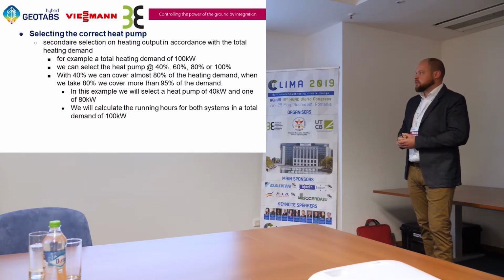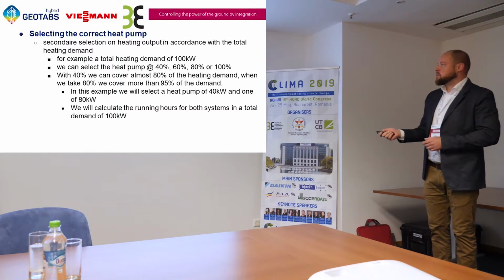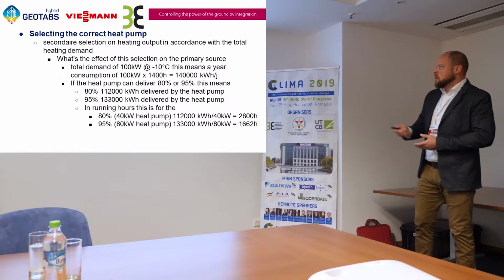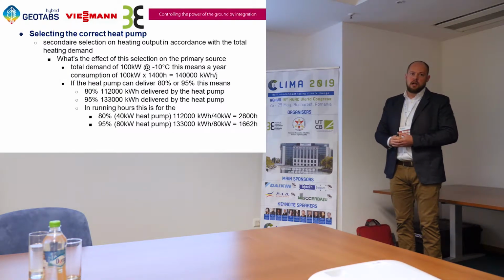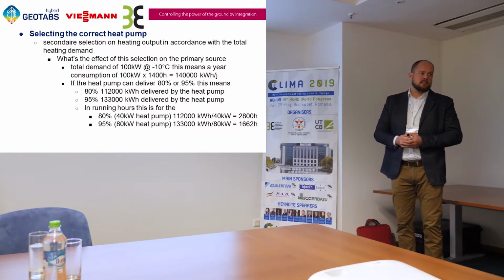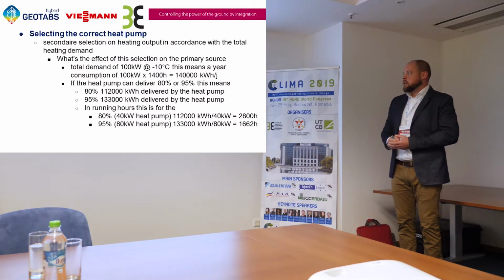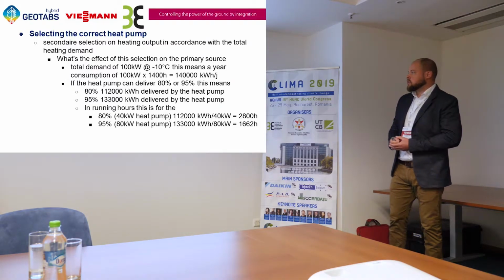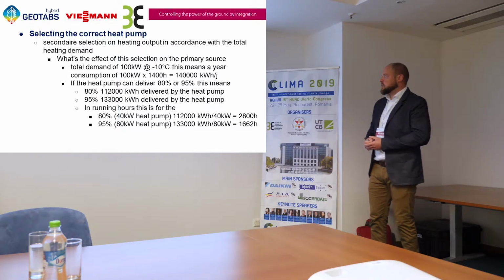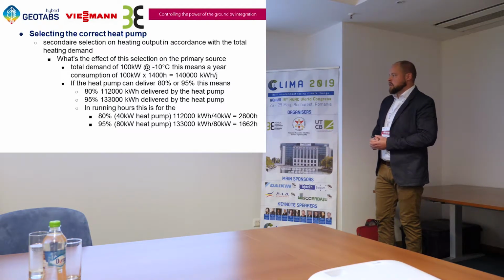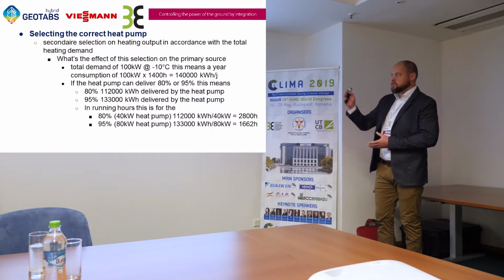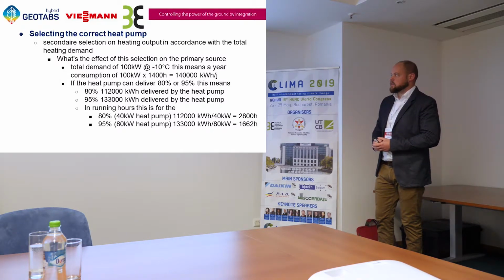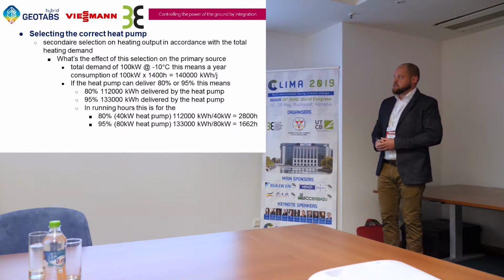And we will see when we calculate the running hours for both systems, that's very important to select the right source. So, for instance, I calculated 1400 hours of total running in a new building. I think it's realistic because it's good insulation, and the running hours are lower than in an older building. So in a total year consumption will be about 140,000 kilowatt hours per year. And if we see here at the curves, we can see that a heat pump of 40 kilowatts can almost deliver 80% of the total. So that means that the heat pump there will deliver 112,000 kilowatt hours of the total energy needed for the building. In the other case, with the 80 kilowatt heat pump, we will deliver 133,000 kilowatt hours by the heat pump.